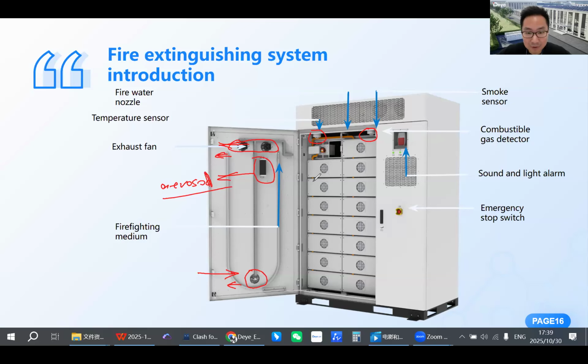It's cabinet level. For every single one of our packs, there's also a pack level aerosol dispenser. So aerosol in our battery pack, aerosol in our compartment. If all this is still not enough to suppress the fire, there is a water sprinkler. It's got temperature sensitive glass inside, similar to the ones we use in our buildings. If the aerosol cannot suppress the fire and the fire starts to go rampant, the glass will break and your water will start spilling out. The water input is in the back. There will be a hose input to supply your water to the sprinkler. And this indicator will give out a visual and audio alarm to your facility for people to evacuate.